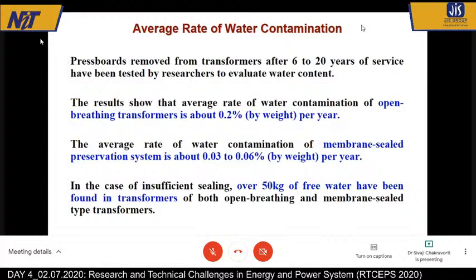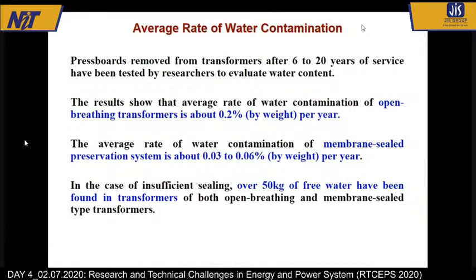Nowadays, all the high voltage, 132 kV or 400 kV transformers are membrane sealed, which means that the top of the conservator tank is not connected to atmospheric air. There is a membrane, so moisture cannot directly come in contact with the oil. And in that case, moisture ingress reduces significantly. It is around 0.06% by weight. It is very, very significantly lowered. But if the sealing part I was talking about, that top cover sealing or oil drain valve sealing, is poor, then a lot of free water can go in, even with the membrane seal. Today we take very special care about that sealing.